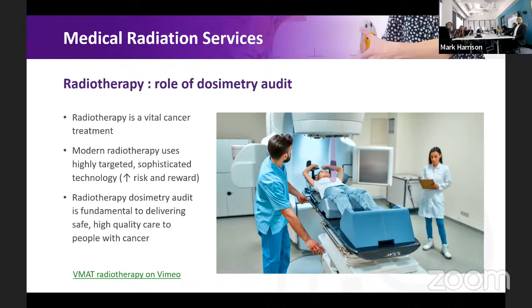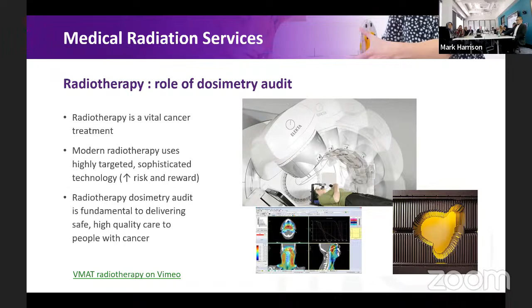And when we look at modern technology, we now have multiple dimensions of freedom. And by that, I mean the gantry can move while it's delivering. The beam can be triggered on or off. The beam current now can be modified in real time. And on the bottom right, you have a picture of an MLC, or multi-leaf collimator. And those leaves can each individually move independent of each other or as a group as part of treatment to deliver a highly sculpted radiation dose delivery to the patient.